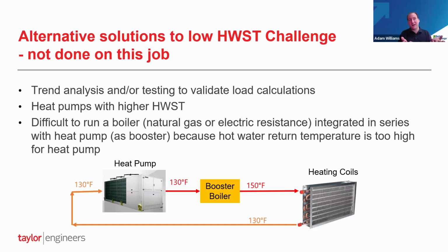Other considerations with that too are that generally non-condensing boilers don't like running at that low temperature. You can prematurely wear out your boiler, and so operators are sometimes concerned about that. Like, hey, are you going to wear out our equipment by running this test? So those are considerations. Also, sometimes your design schedule doesn't really accommodate running a test early in a winter morning.